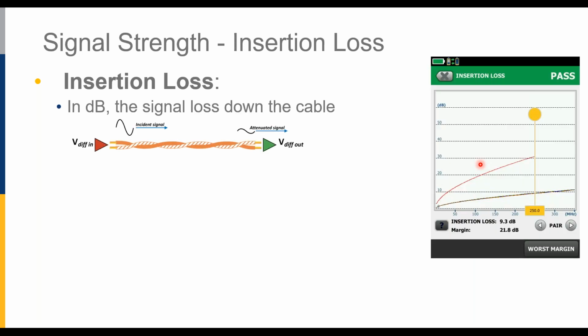So after that, what we're going to look at is the signal strength, and actually we're going to measure how much loss there is in the signal. We're going to inject a given signal into the cable, and we'll measure on the far end the attenuated or reduced signal, the reduced amplitude. We get a graph like this that shows the strength of the signal versus the frequency that we're operating at. This red line here represents the limit line from the standards.